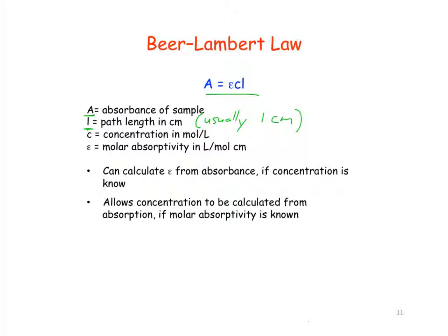Right, it has to be transparent to the light we're measuring over. So you can't just use normal glass because it would absorb the ultraviolet light. So usually in the ultraviolet, these things are made out of quartz, and they're polished up really nice. And they can't have little wavy things that would bend and diffract the light off. It's got to be high precision quartz.